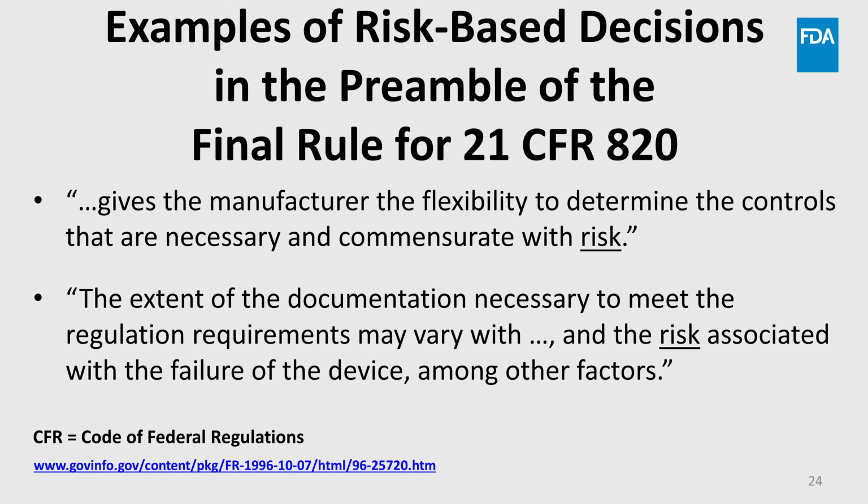In a discussion on removing the term critical device in 1996, FDA stated, "In fact, the new regulation is less prescriptive and gives the manufacturer the flexibility to determine the controls that are necessary commensurate with risk." Who determines that risk and the controls required? You. You make that determination, and you are to use risk in doing it.